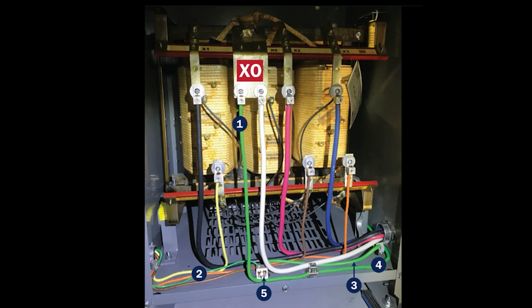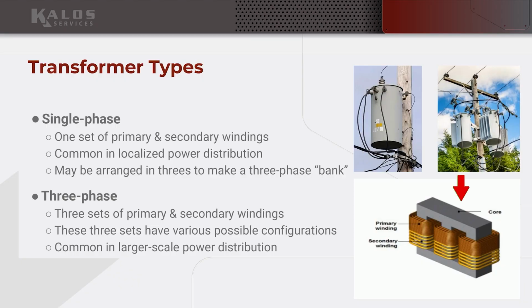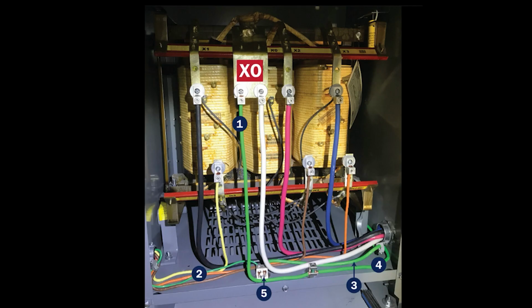Here's an illustration that looks like something we're all used to seeing - a three-phase transformer, maybe a 45 kVA, I don't know the size. You can see past the wires these big blocks, which are the windings. What you can't see in the photo is that those are wound over the iron core. Comparing this photo to the other, you can see the relationship and how it's constructed. This three-phase transformer is simply three single-phase transformers wired together.